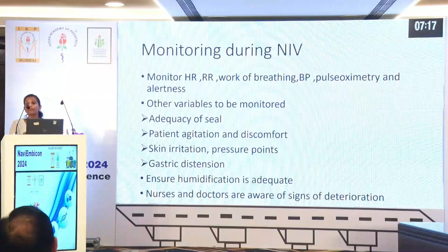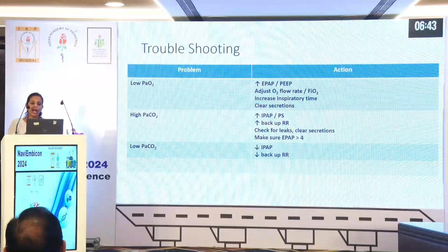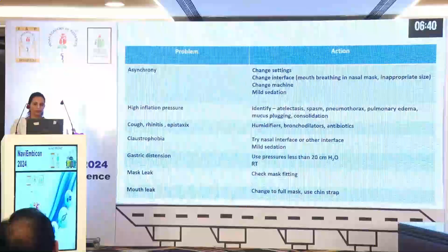Now, troubleshooting on NIV. If there is low PaO2, you will increase the EPAP, or you will increase the FiO2. You can increase the inspiratory time or clear secretions. If there is high PaCO2, you will increase the IPAP. You will increase the backup rate. You will check for leaks and clear secretions. You can make sure that EPAP is above 4. If there is low PaCO2, you would decrease the IPAP and decrease the backup respiratory rate.